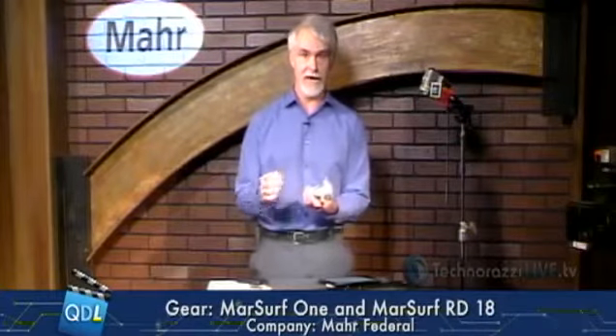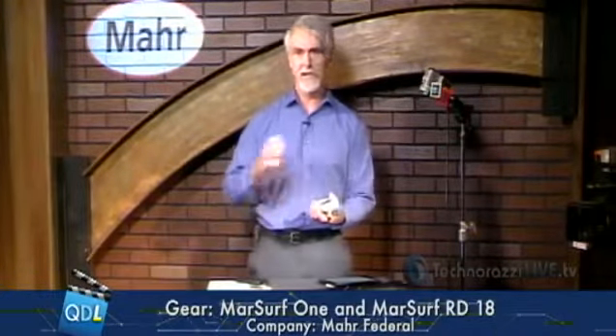But there's another thing. Let's go back to our regular camera here, Daniel. The other thing that's really cool about this, one thing I'm seeing more and more in portable devices, is where the calibration reference is stored within the device itself. Now, if you've used some older surface measurement devices, and comes time you need to calibrate them, you know what you do. You go to your tool crib, you take out your little plastic box that has your surface reference tabs in them, you bring them back to the tool, you put them down, you handle them very carefully because they're typically small, and you try not to damage or scratch them. You take your calibration measurements, put them back in the case, put them back in the tool crib. That's all very nice and well, unless you lose those references or unless you scratch them or get something on them. Much better if the reference is stored inside.